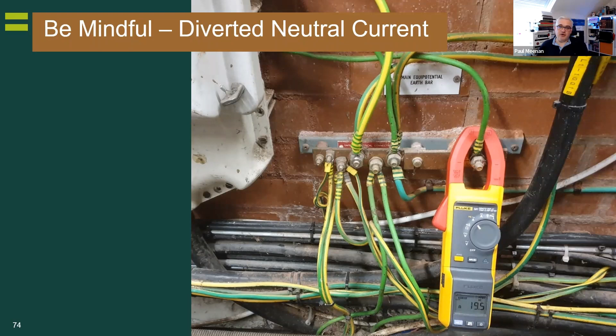The reason I said that is because Guidance Note 3, which has been rewritten, in section 333 or Appendix D, there's this wonderful check for diverted neutral currents. And if anyone knows me, you'll know I've been blithering on about diverted neutrals for some years. That's an earthing conductor for an installation with 20 amps on the earthing conductor. Even when I isolate the installation, I can still get 20 amps. So it's network neutral current, finding another path. And so I've done a simple diagram for what that actually means in simple terms.